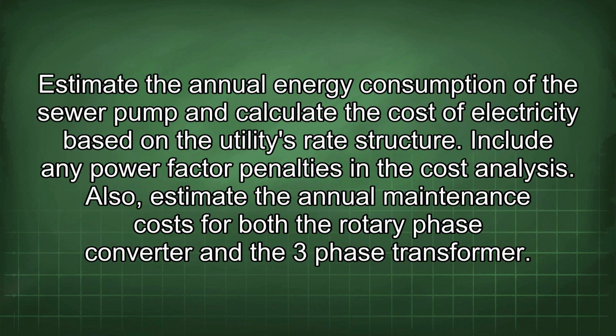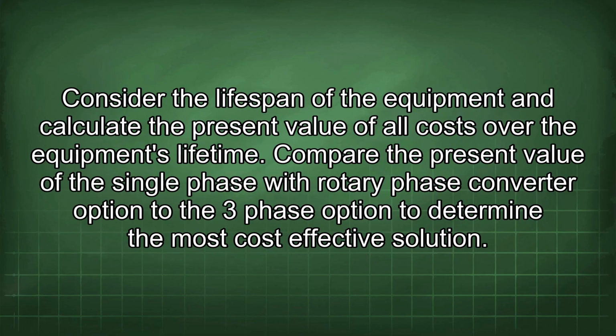Estimate the annual energy consumption of the sewer pump and calculate the cost of electricity based on the utility's rate structure. Include any power factor penalties in the cost analysis. Also, estimate the annual maintenance costs for both the rotary phase converter and the 3-phase transformer. Consider the lifespan of the equipment and calculate the present value of all costs over the equipment's lifetime.